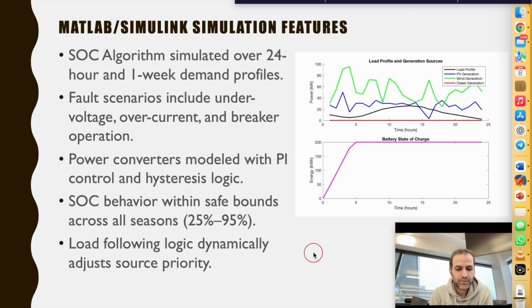We also had the SOC behavior within safe bounds across all seasons, around 20% to 95%. The battery's state of charge remained within a safe operational range of 25% to 95% across all seasonal profiles. This reflects proper sizing and load balancing in the hybrid setup, avoiding deep discharge or overcharging conditions throughout the year.